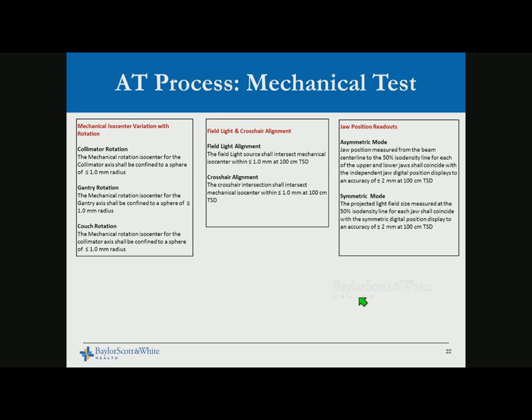Mechanical tests include various categories that we typically adopt from vendor-recommended tests into our periodic QA. Mechanical isocenter verification with gantry rotation, collimator rotation, and couch rotation all have tolerances. Light field and crosshair alignment, jaw readouts — on a TrueBeam there is no digital readout at the console or mechanical markings, it's all electronic; on a C-series machine there are both mechanical and digital readouts that must be within tolerance.